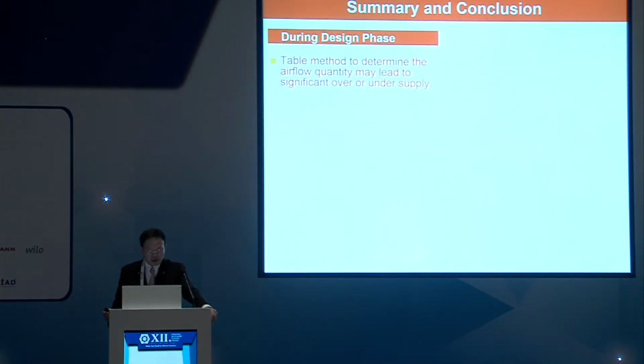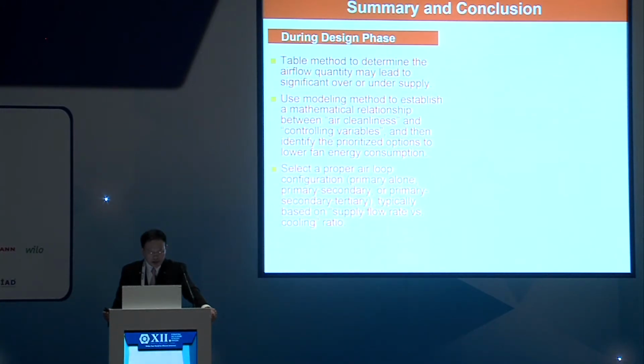As a summary, during the design phase, the table method to determine airflow quantity may lead to significant over or under supply. Most of the time it may be over, but if you simply use the tables, there is an 80% chance you may overkill. So use the modeling method to establish a mathematical relationship between the air cleanliness and the control variables, and then identify the prioritized options to lower fan energy consumption. Select a proper air loop configuration, primary alone, or primary, secondary, tertiary, between the supply airflow versus the cooling load. And you can also use CFD to assist and optimize the design.